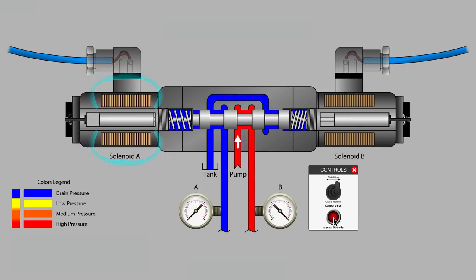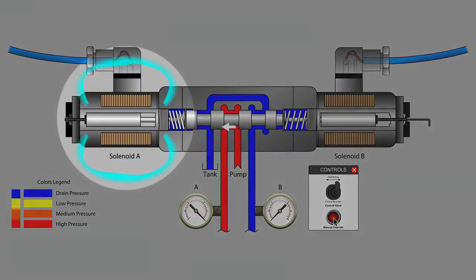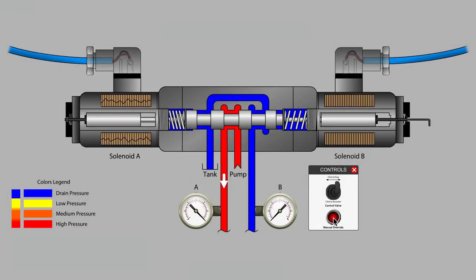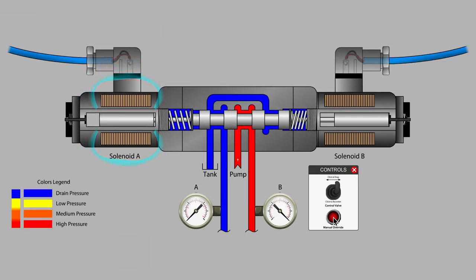As the mechanical override feature is more mechanically forceful than the electromagnetic forces of a solenoid, the armature in solenoid A is being pushed outward from the coil center position, increasing the size of the magnetic field which in turn increases the amount of current running through the coil.